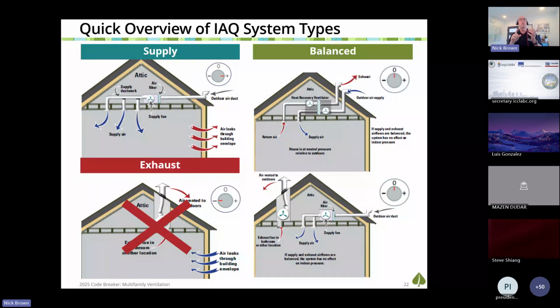Last code cycle, if you were following the energy code, multifamily builders had the choice of balanced ventilation or exhaust ventilation with blower door testing of the units to show that they're tight. And I thought most multifamily builders, to avoid blower door testing, would install balanced ventilation systems. By and large, I was dead wrong. Most of them chose to continue installing exhaust ventilation and do the blower door testing. But now here we are in the 2025 code cycle, and what's required, which I'll cover in a minute, is balanced ventilation or supply ventilation and blower door testing of the envelope.